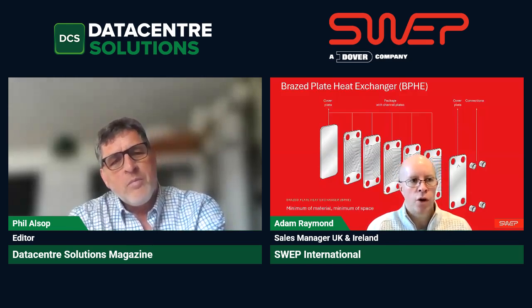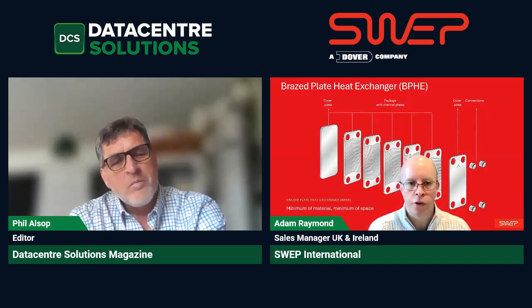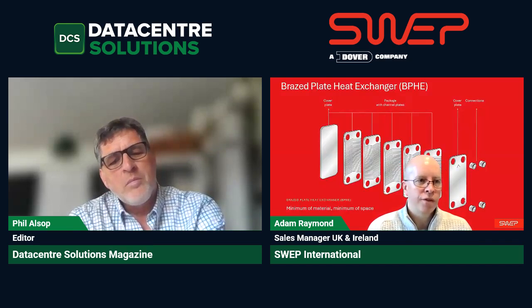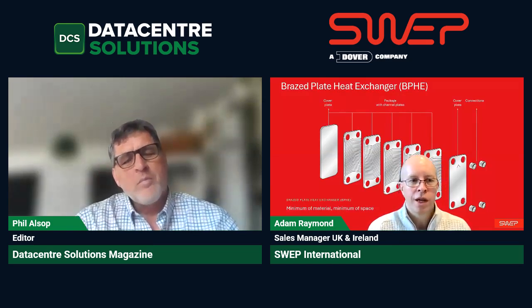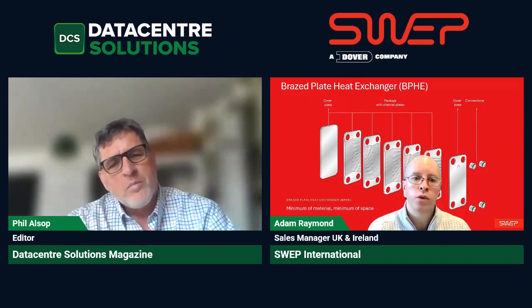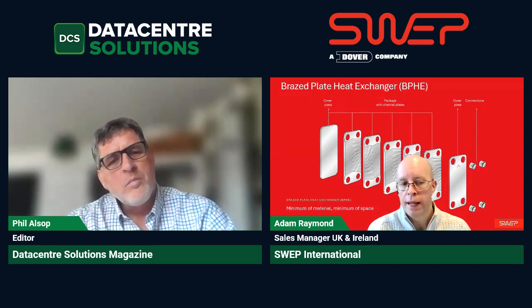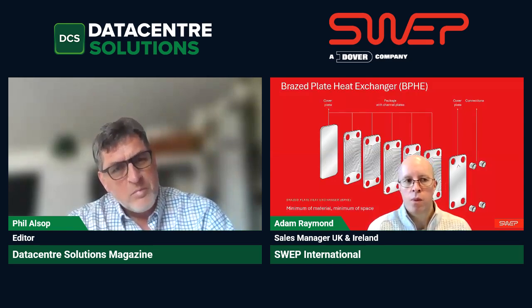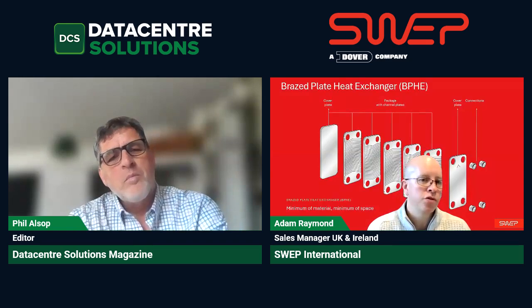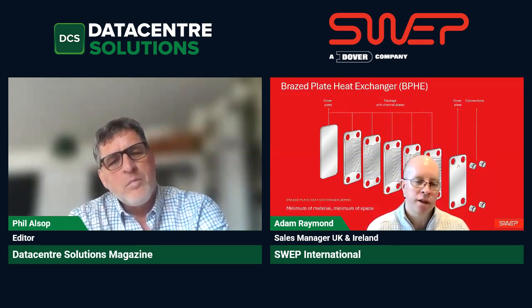But then you've got the challenges of quite large amounts of the cooling fluid, which is dielectric - non-conductive - and there's concerns about that at various levels. There's the chemical concern - what are these fluids containing? PFAS is quite a hot topic at the moment, these so-called forever chemicals. So some of these refrigerants and liquids being used for single and two-phase immersion - there's uncertainty about whether they might be restricted in the future. So again, it's back to that future-proofing thing with immersion cooling.